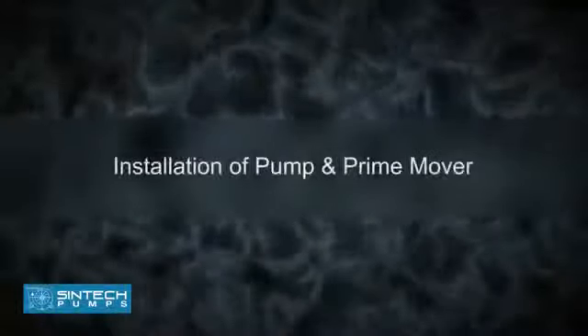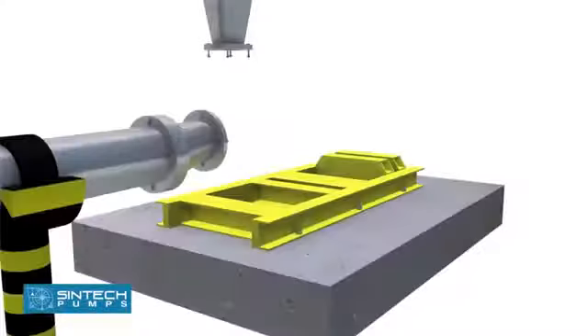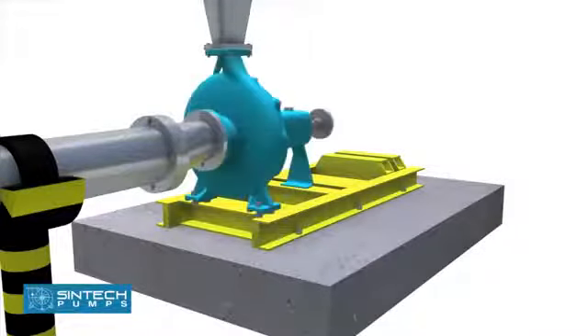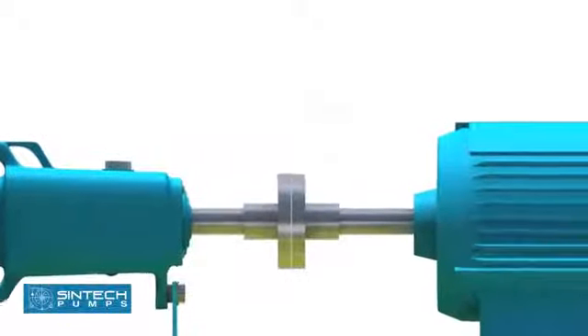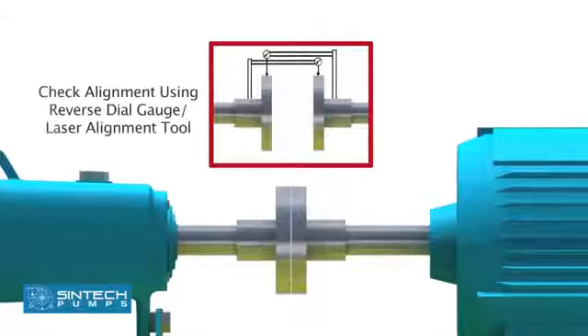Installation of pump and prime mover: The pump and motor unit needs to be fitted firmly onto the base frame using nuts and bolts before fitting in any pipes. It is essential to confirm the distance between the shaft ends. In the subsequent step, the pump and motor are aligned to the final tolerance using a reverse dial gauge or laser alignment tool.